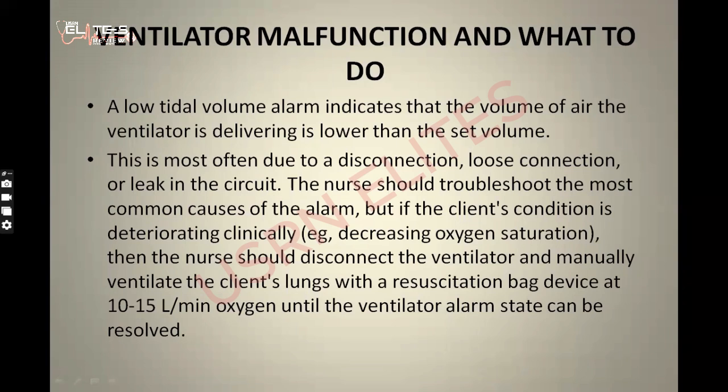So that's the general rule I want us to take note of. Okay. Now let's look at what we have here. A low tidal volume alarm indicates that the volume of air the ventilator is delivering is lower than the set volume.